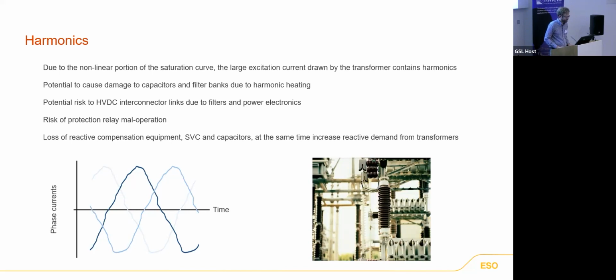that chart there. So that has a potential to cause damage to capacitors, filter banks due to harmonic heating. There's also a potential risk to HVDC equipment, interconnectors, due to the fact that they use filters and power electronics to convert the AC into a DC. There's also a risk of protection relays maloperating.